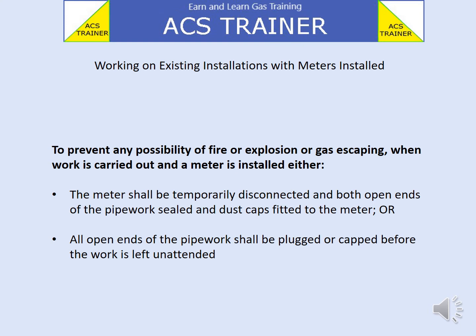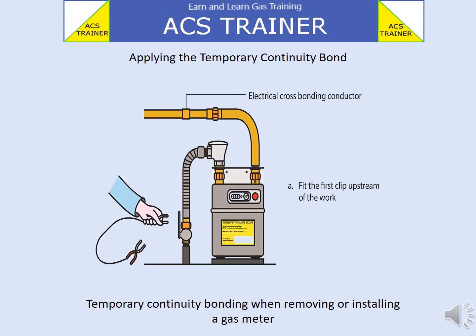When work is carried out and a meter is installed, either the meter shall be temporarily disconnected and both open ends of the pipework sealed and dust caps fitted to the meter, or all open ends of the pipework shall be plugged or capped before the work is left unattended.